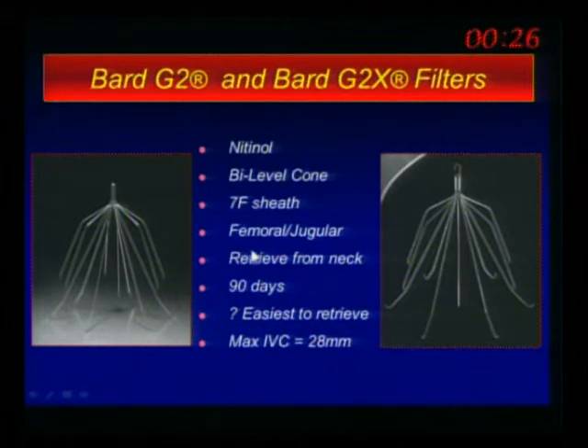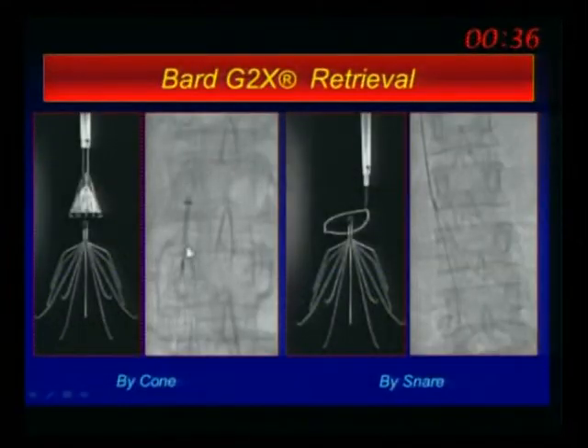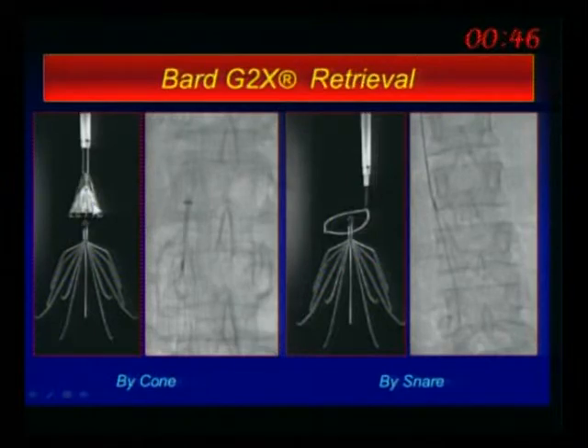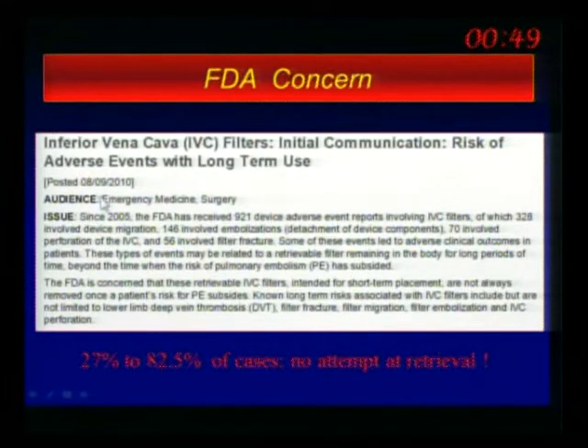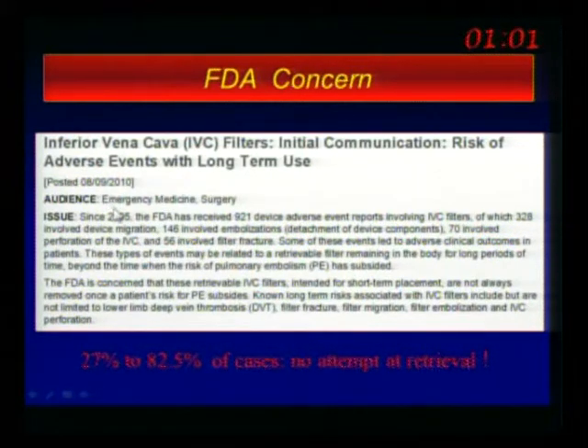The BARD G1 came off the market because it was embolizing — the limbs were fracturing. There's a big issue with newer filters and limb fracturing, so we have to be very careful. You have to retrieve it if that was the plan. The retrieval technique uses a snare or a cup catheter — it's easier to get it with a cup. You can put a balloon from below to push the hook out of the vena cava wall. There are different types of snares and biopsy forceps you can use.